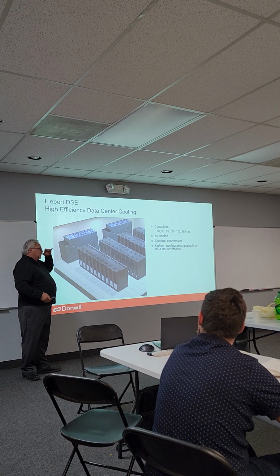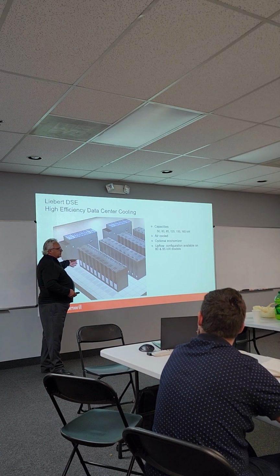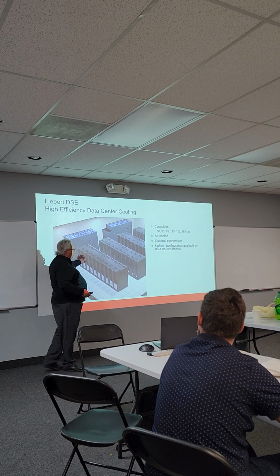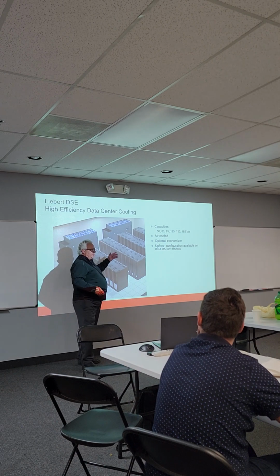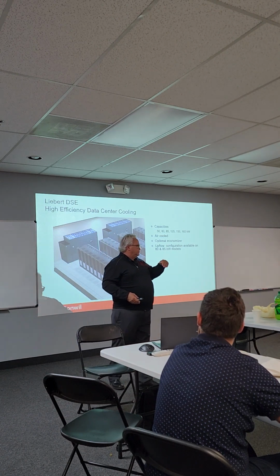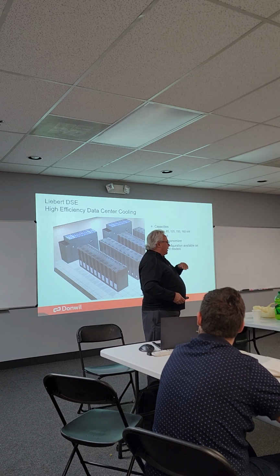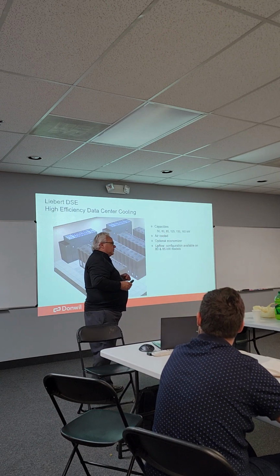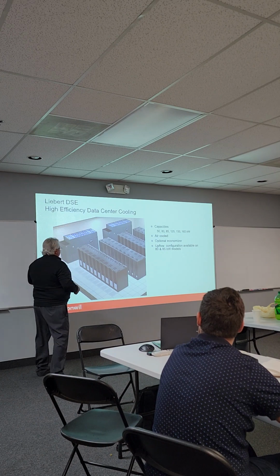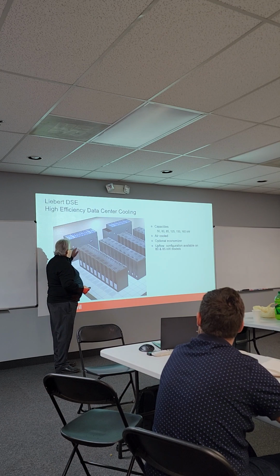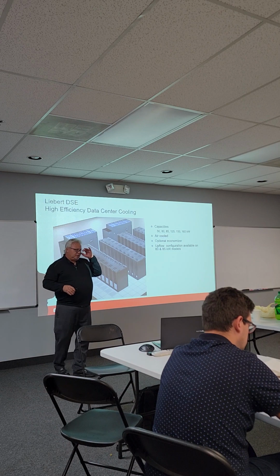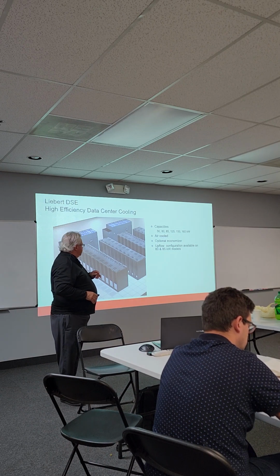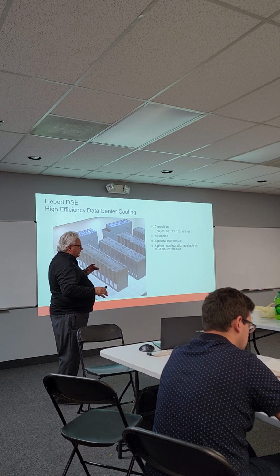So what would happen if I'm already at set point at 72 degrees and this thing says I need to dehumidify, but the customer doesn't have the load to support the cooling? You could see what would happen, right? Temperature would go down. Right. And it would keep going down, and then you'd have a major problem on your hands, because once you get below 68 degrees, you look on a psychrometric chart, humidity actually starts to go up. So it snowballs. What you try to do is match this equipment as close as you can to the load. If you do that, the reheats in the unit will stabilize the room air temperature. That's the only reason we put reheat in our unit, to stabilize room air temperature. That kind of makes sense, right?